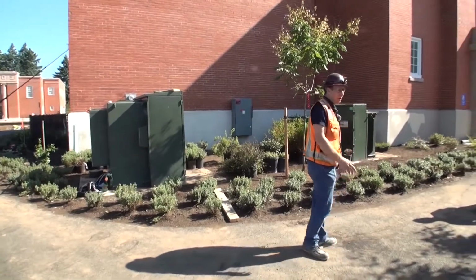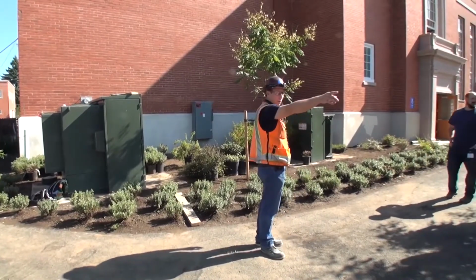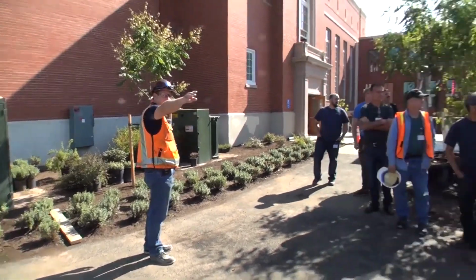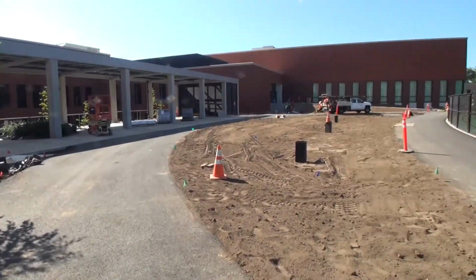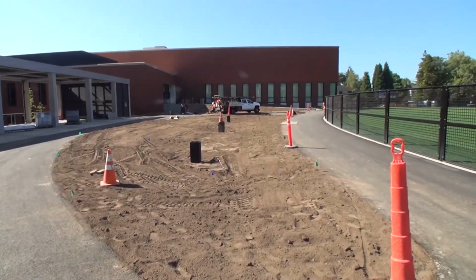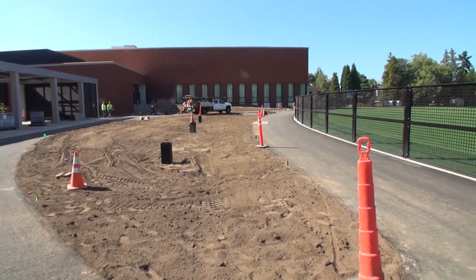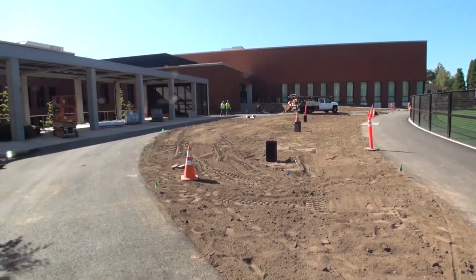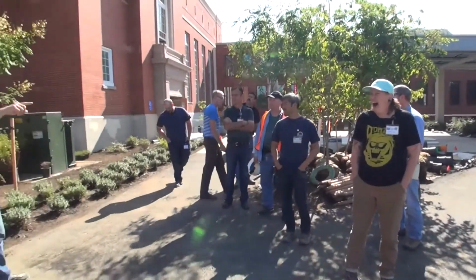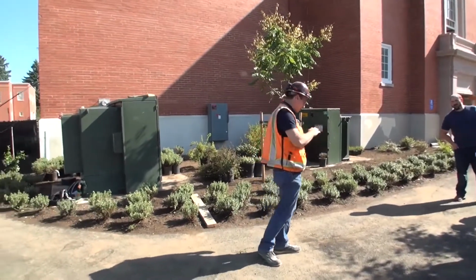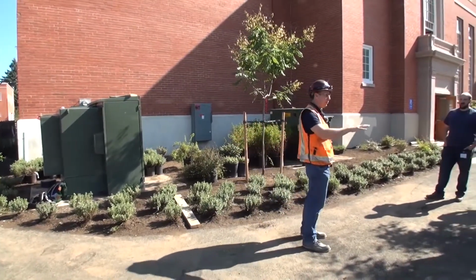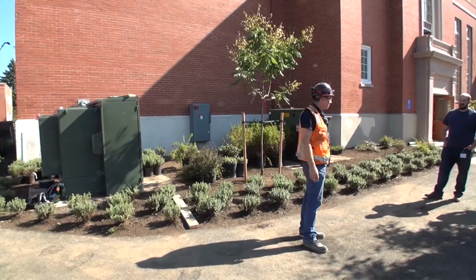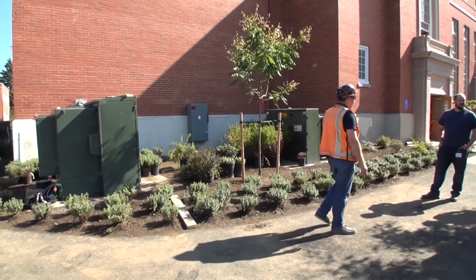So this power route essentially comes in to where that white truck is, and it zigzags over, then goes straight on the west side of the gym all the way to the street. There's a power pole there that the primary comes up, so that's the route it comes in. It has warning tape on top, and it's buried in red CDF. That's the main shut-off for the building, that pole. That will kill the whole building, yeah.